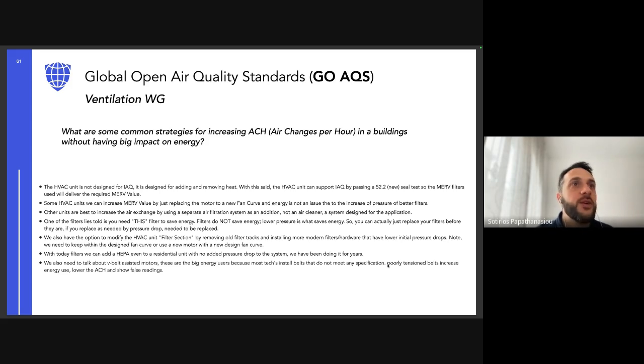Okay, we also have the option to modify the HVAC unit filter section by removing old filter tracks and installing more modern filter hardware that has lower initial pressure drop. Note, we need to keep within the designed fan curve or use a new motor with a new designed fan curve. With the filters, we can add a HEPA even to the residential unit with no additional pressure drop to the system. We have been doing this for a year, and we also need to talk about the V-belt assist motors.